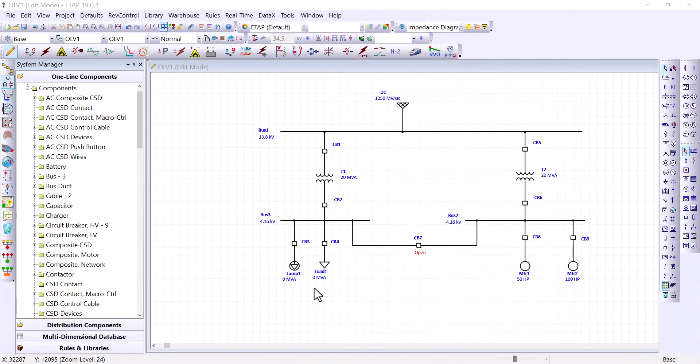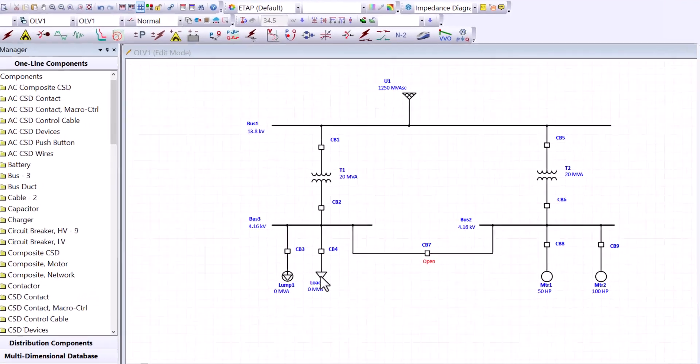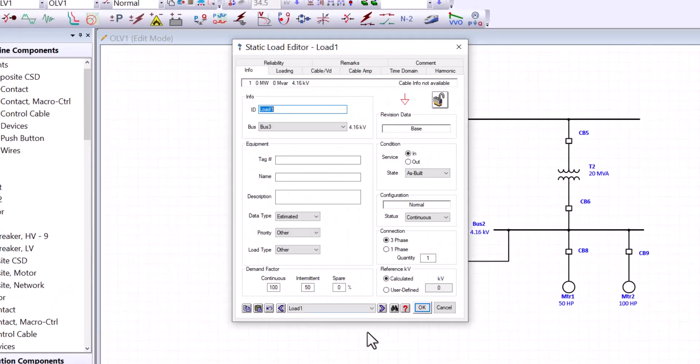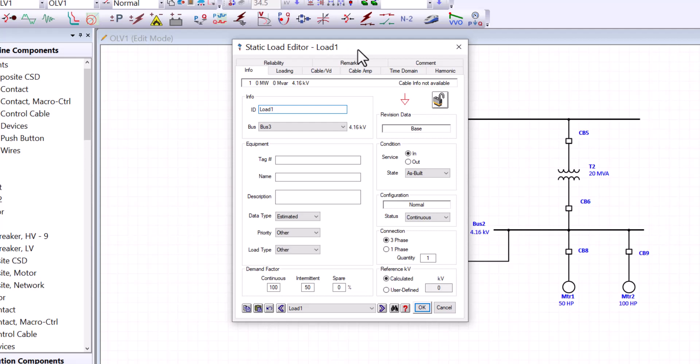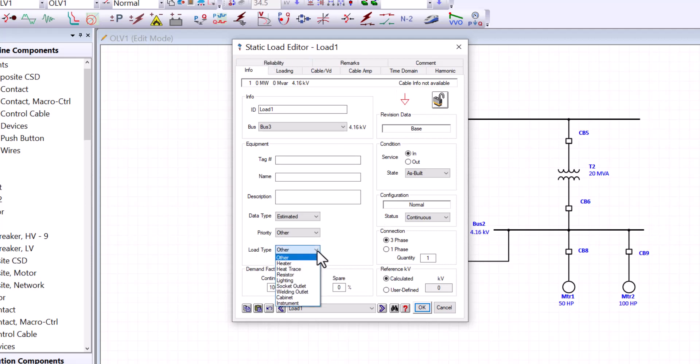The next component we should discuss is static loads. And if we go to bus three, load one here is a static load. And by definition, static loads are considered constant impedance loads. And they follow Ohm's law. Since power equals V square over R, that means the input power increases proportionally to the square of the input voltage. And to look at the properties of a static load, there is nothing really new here. But we should look at what type of load can be a static load.